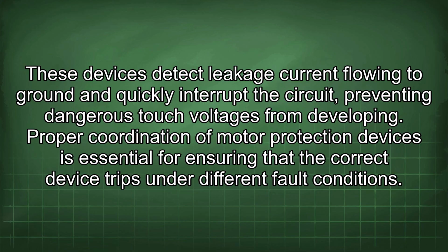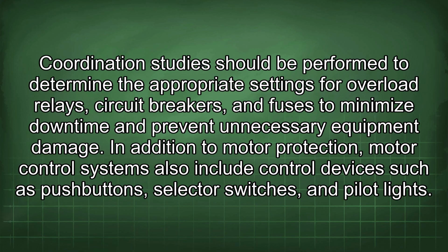Proper coordination of motor protection devices is essential for ensuring that the correct device trips under different fault conditions. Coordination studies should be performed to determine the appropriate settings for overload relays, circuit breakers, and fuses to minimize downtime and prevent unnecessary equipment damage.